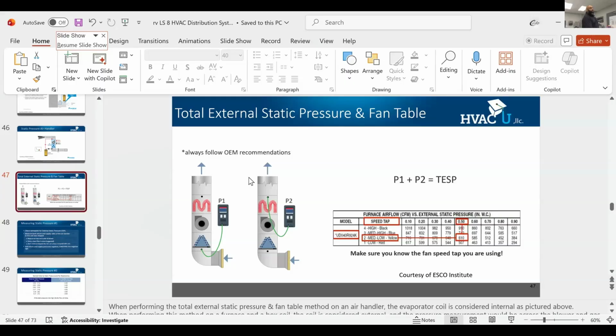Let's discuss the rating. Furnaces are rated and tested at 0.5 inches of water column. The test rating pressure, that's what they're rated at. Oftentimes, when you put in an indoor coil for a heat pump or an evaporator coil, the duct procedures have you design static for 0.7. So 0.5 isn't a number to design to; it's what the furnaces are tested at.